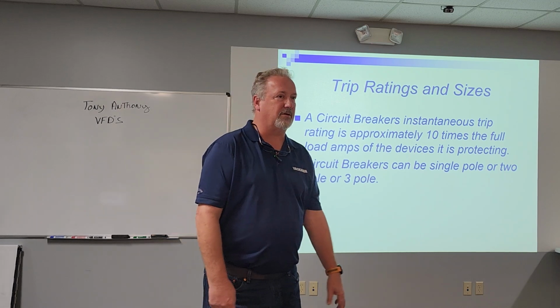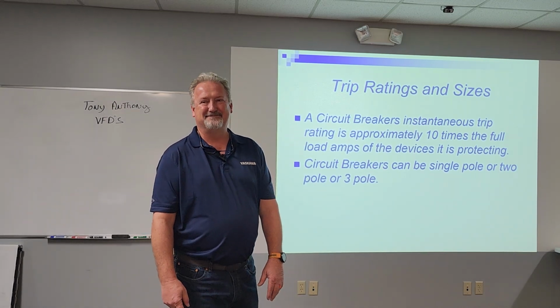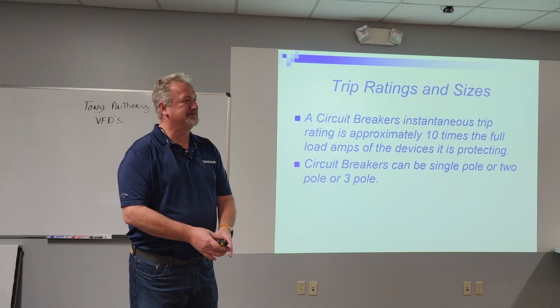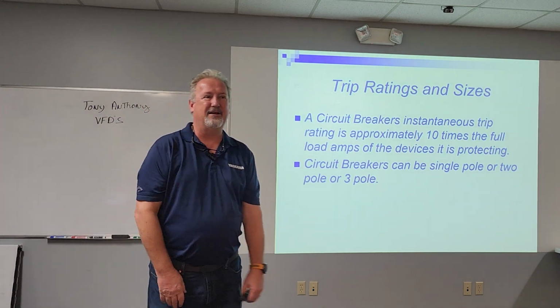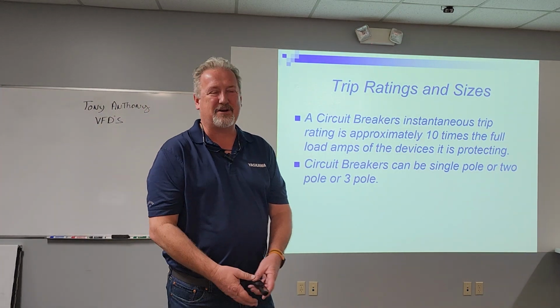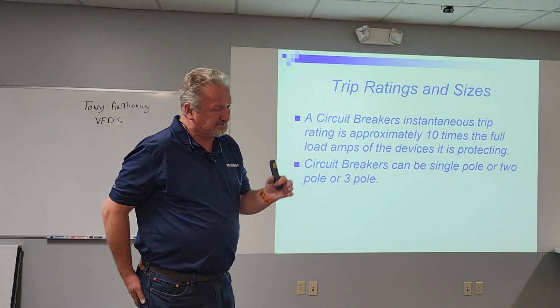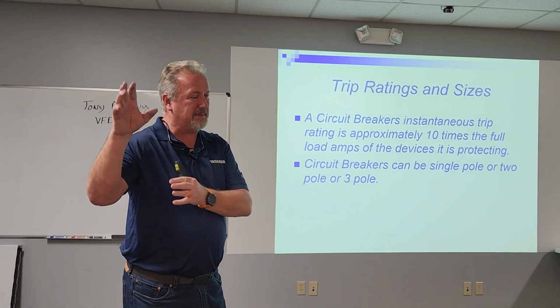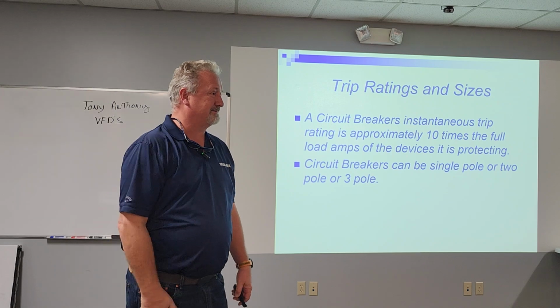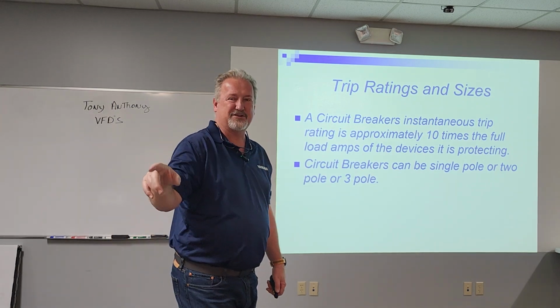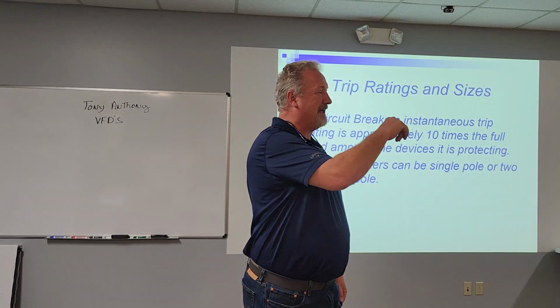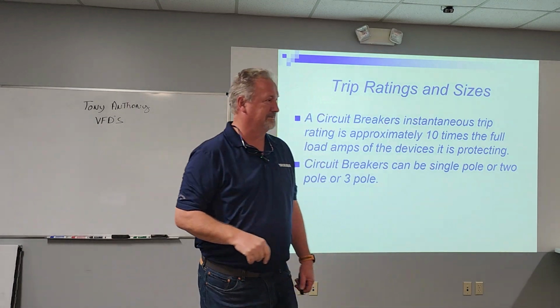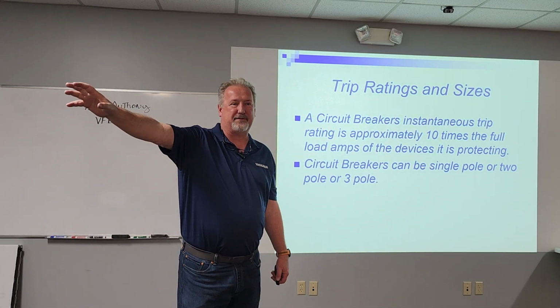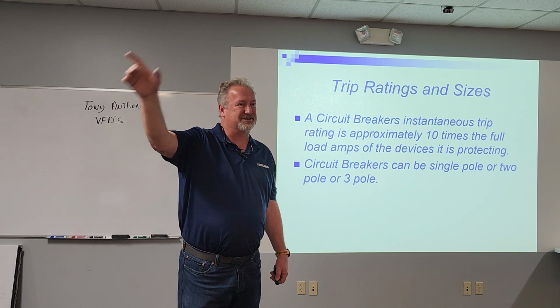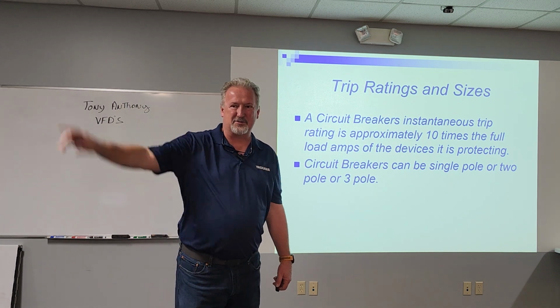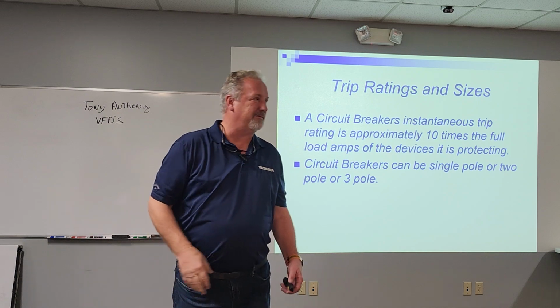Well, what happens occasionally with a boiler? You pop a relief valve. They popped a relief, and all that water came down on the drives. It tripped the drives off. It fried the drives. Well, whoever had run the panel had just used regular breakers. Those breakers didn't trip fast enough. They actually tripped the 800 amp main feeding the whole school instead of the 40 or 50 amp breakers on the wall, because that tripped quicker. The surge was so fast, they got the main before those tripped.